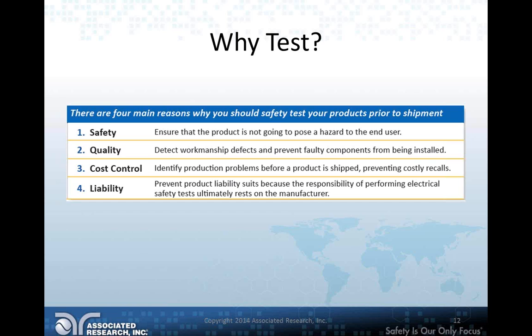And then, of course, what flows from that is liability. You want to protect against product liability suits, because the responsibility of performing the electrical test ultimately rests on the manufacturer, you guys. It's going to come back on you if it shows that a test has not been done properly. We've even run into situations where people thought they were doing their test properly, and then upon further review, it turns out that they weren't even running a proper hipot test. So, like I said, next time we're going to cover more of the testing itself, but that just goes into making sure not only that your operators are safe, but that they're doing the tests right.